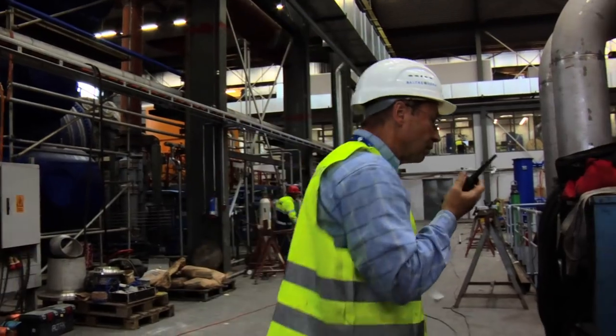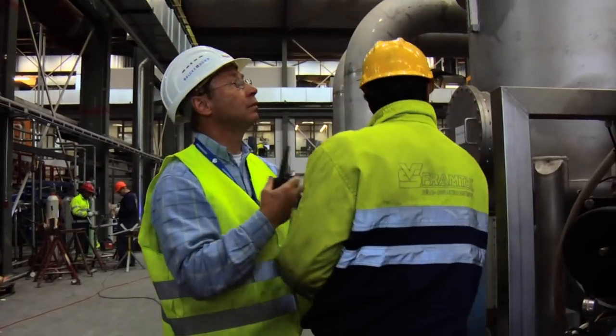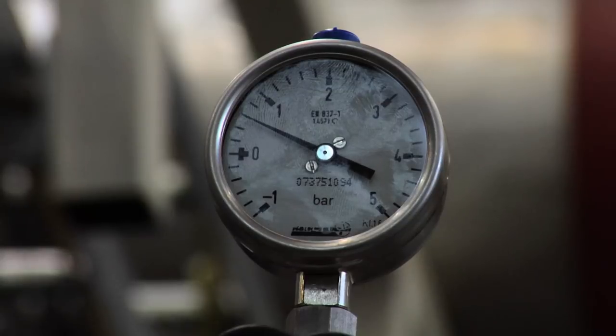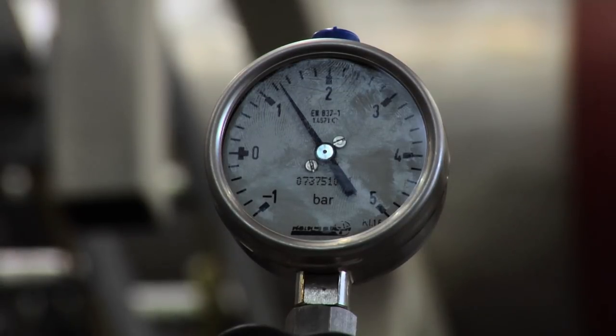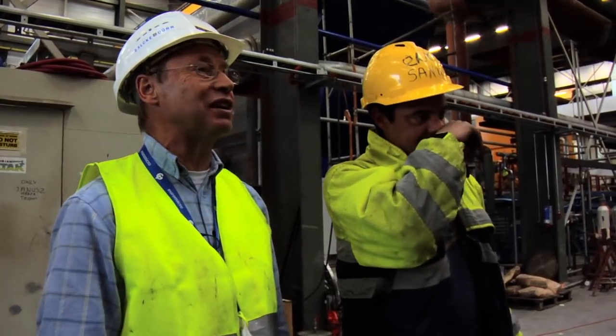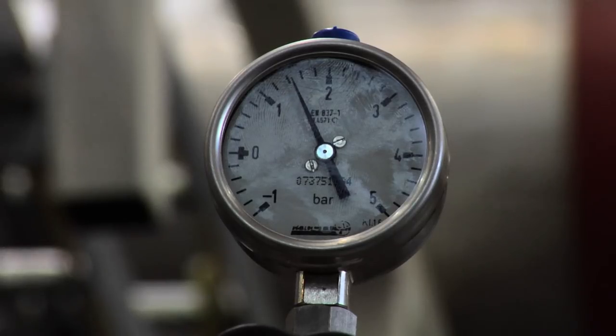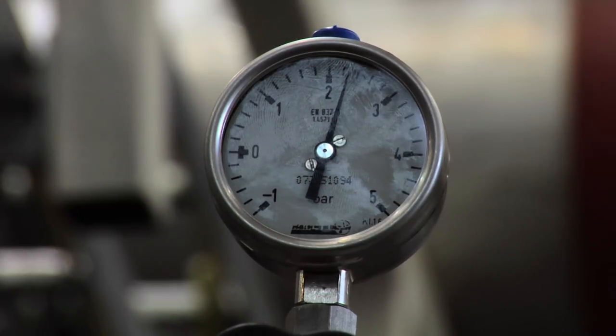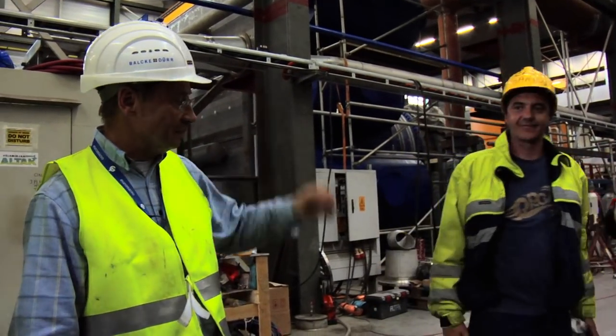Here, look. Now we have the pressure. This damn valve needed a kick. There were a lot of ghosts in this area. Maybe. But now we have the pressure, all things are okay. The problem was that maybe something had forced this flap into closed position. And now, when we have opened it, having moved it a little bit, it has gone now into open position. It's now running well. Okay, it's running well, fine.